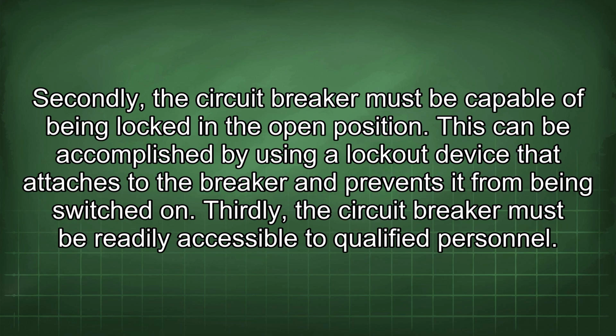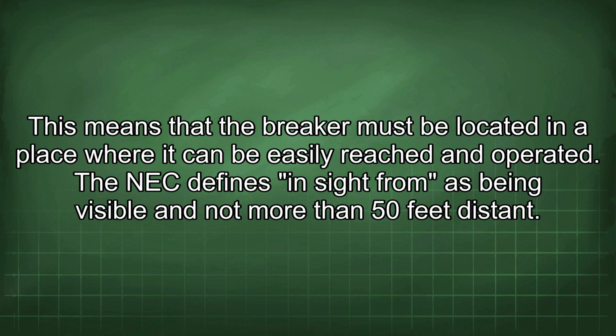This can be accomplished by using a lockout device that attaches to the breaker and prevents it from being switched on. Thirdly, the circuit breaker must be readily accessible to qualified personnel. This means that the breaker must be located in a place where it can be easily reached and operated. The NEC defines "in sight from" as being visible and not more than 50 feet distant.